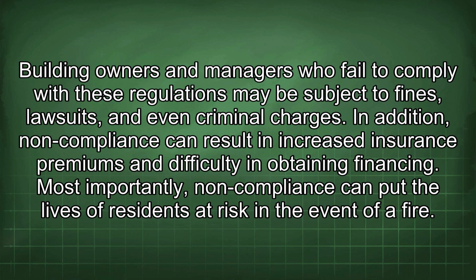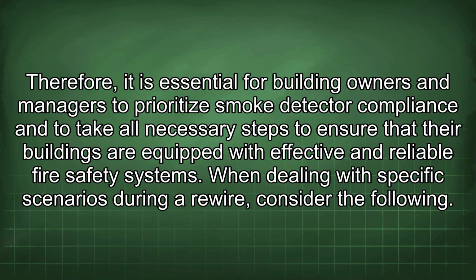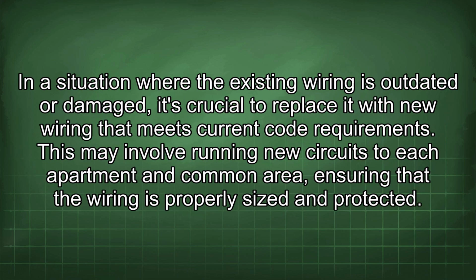Most importantly, non-compliance can put the lives of residents at risk in the event of a fire. Therefore, it is essential for building owners and managers to prioritize smoke detector compliance and to take all necessary steps to ensure that their buildings are equipped with effective and reliable fire safety systems. When dealing with specific scenarios during a rewire, consider the following. In a situation where the existing wiring is outdated or damaged, it's crucial to replace it with new wiring that meets current code requirements. This may involve running new circuits to each apartment and common area, ensuring that the wiring is properly sized and protected.